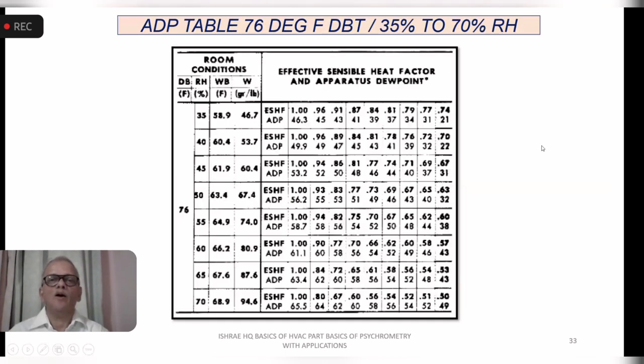So this is a sample of the ADP table. This is the effective sensible heat factor, ESHF, and apparatus dew point table taken from Carrier system design. You have the room conditions. I have picked up only one sample as the room condition, a popular 76 degrees Fahrenheit. You will find all units in IP units now. You have a range of humidity from 35 to 70 in steps of 5%. So 76 degrees with 35, 40, 45 percent RH. The corresponding wet bulb temperature is given. So from the combination of room dry bulb and percentage RH, you get the wet bulb and the W, which is the grains per pound or the humidity ratio, which is here.